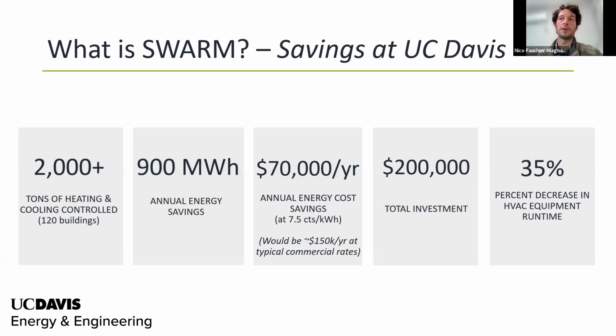Yeah, there is definitely some variation from one building to the other. I would say it's pretty rare to find a programmable thermostat that is correctly programmed with the right date and time, and where that gets maintained over time. So your base case is more often than not going to be longer run hours than what's needed, and probably less comfort than what you would expect. But yeah, there's definitely some variability. It's kind of hard to say. I don't have the numbers in my head of percentage, but you would probably get at least 10-15% at the very least in savings, and up to that 40% we saw for HECR. I think that's a pretty typical range.